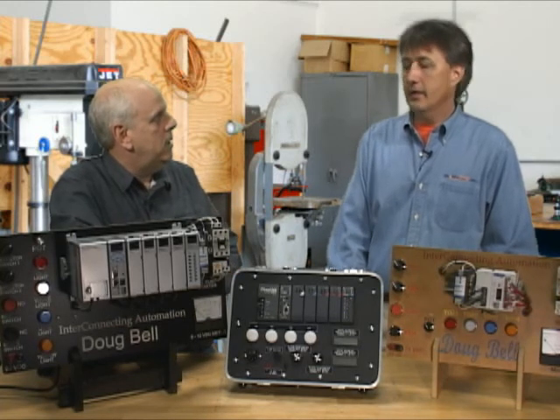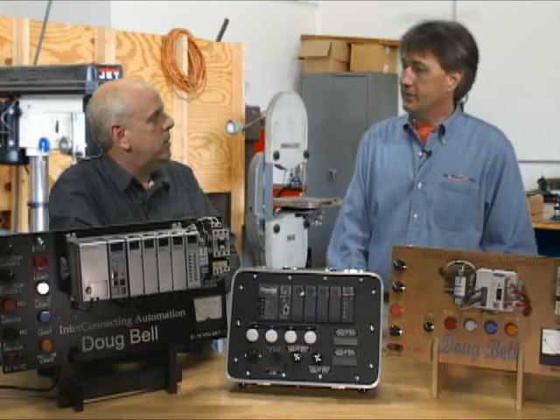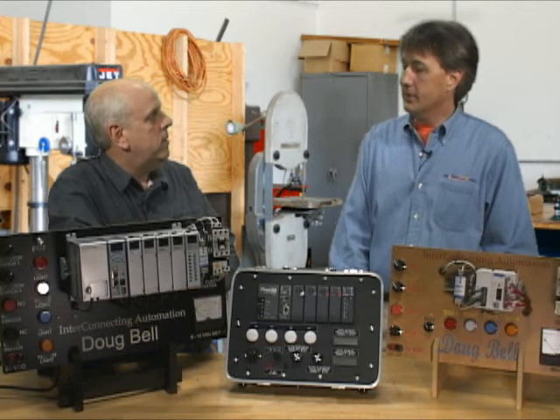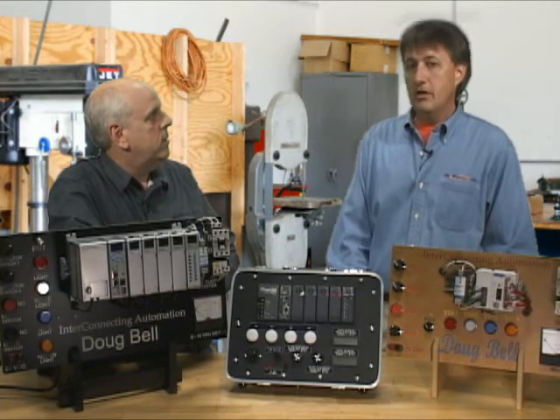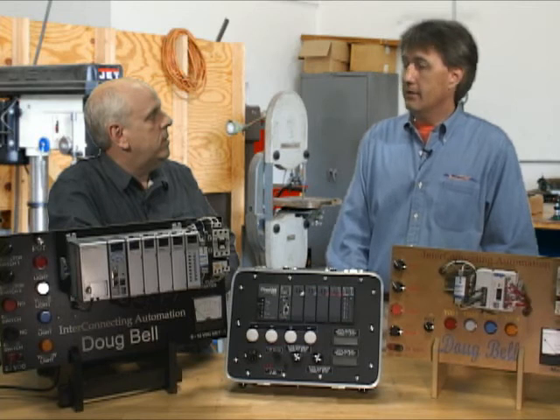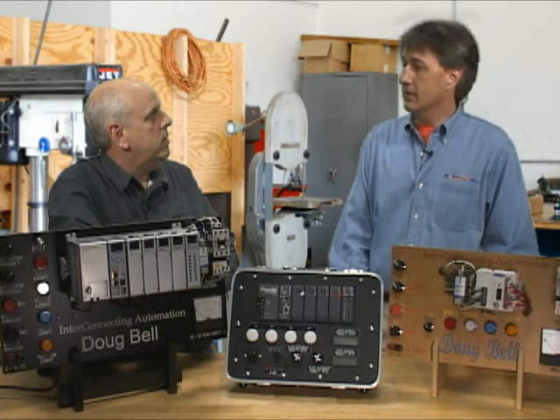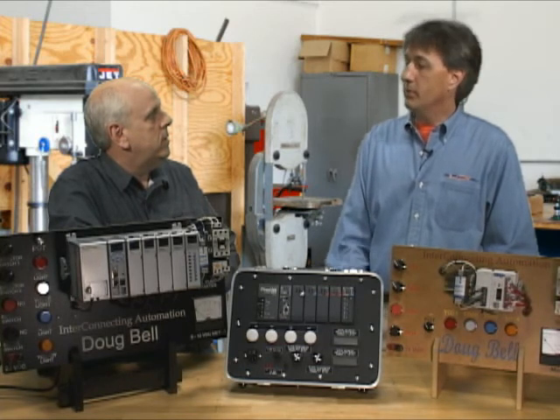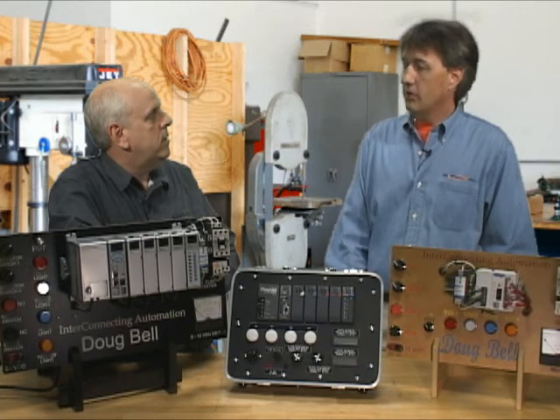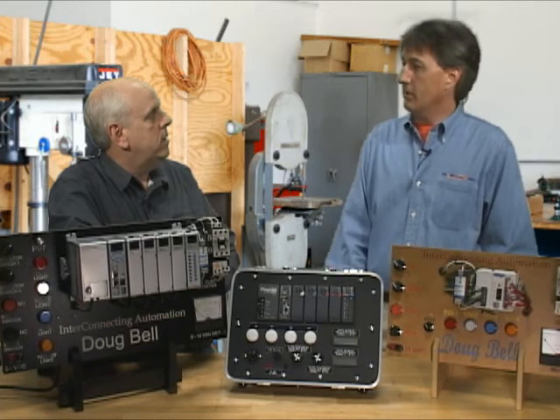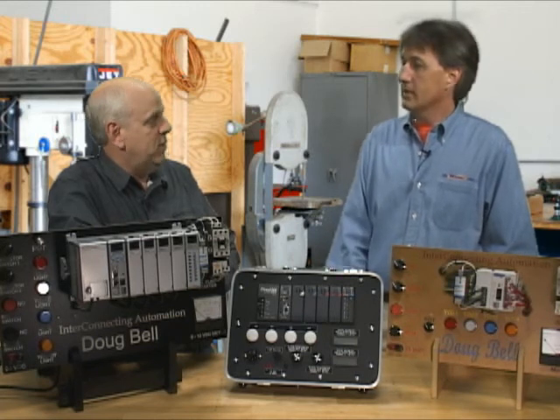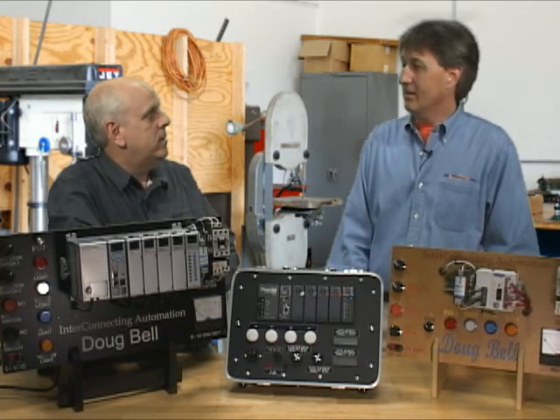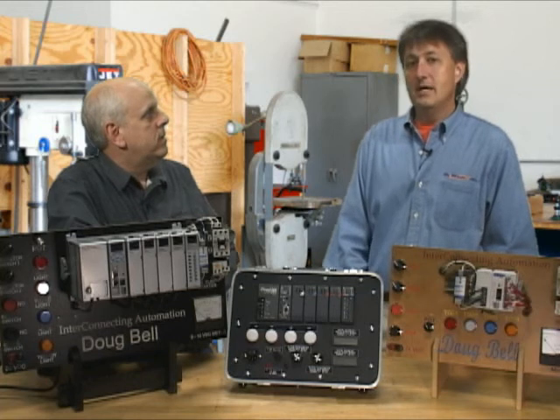Good question, Doug. Basically in the PLC ladder logic you have to create a rung of logic using the WX instruction and you've got to activate that rung. The best way to do that is either through a rising edge or through a one-shot, because if you don't put a rising edge in there, it'll keep sending data constantly every time that rung runs, every scan, and it can cause a lot of data to be stored at one time.